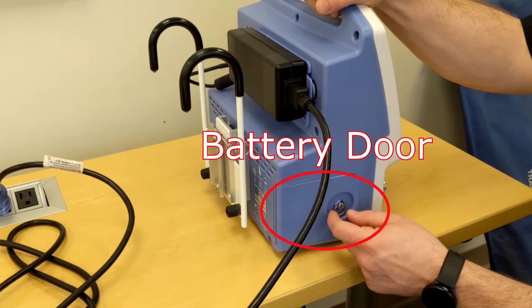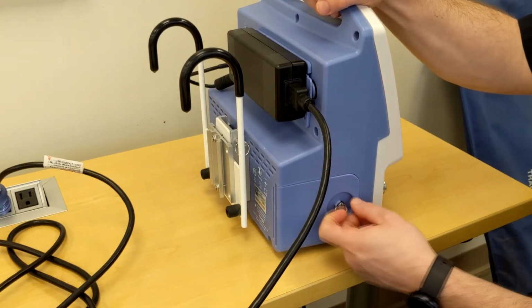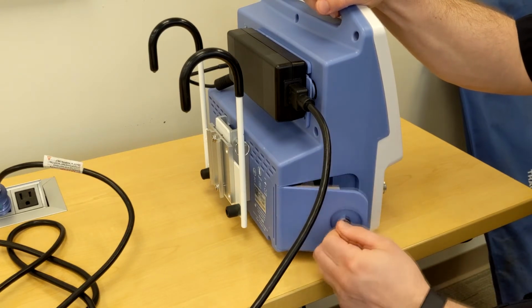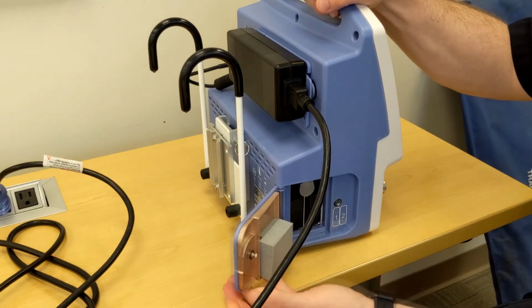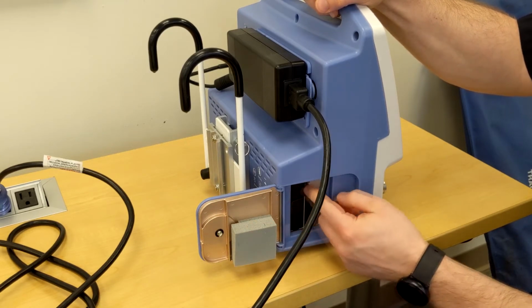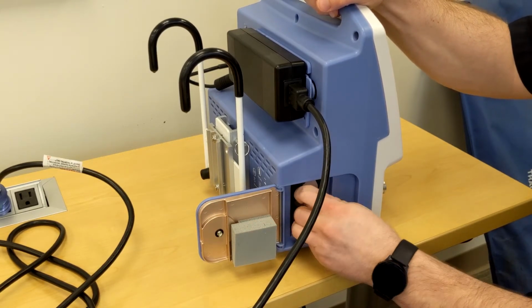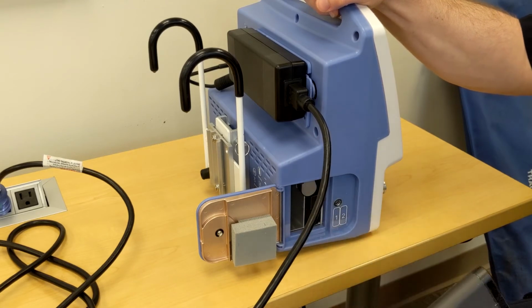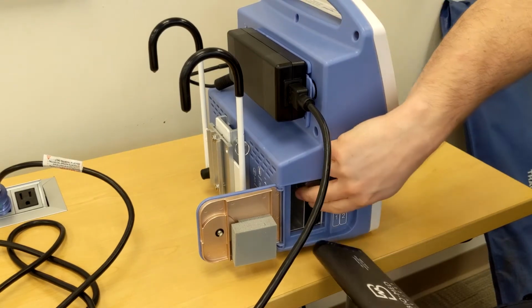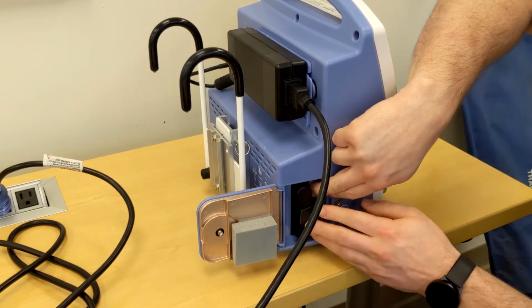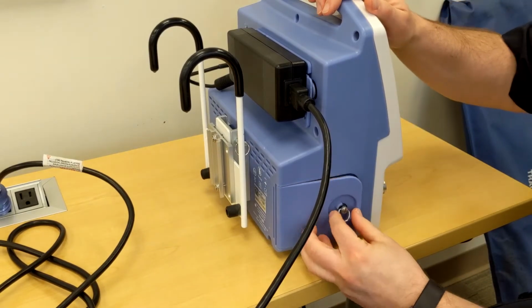On the left hand of the ventilator is the battery door. Turn the screw counterclockwise to open this door. Behind this door, we will find two removable batteries. Battery 1 is located on the left and battery 2 is on the right. To remove the batteries, slide the metal piece to either direction and then pull the tab on the edge of the battery. The TV-100 is capable of approximately 7 hours of operation with fully charged batteries under typical patient parameters.